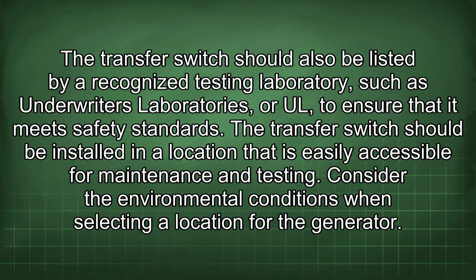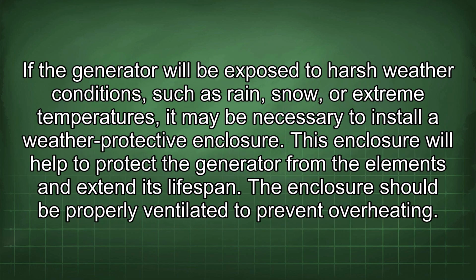Consider the environmental conditions when selecting a location for the generator. If the generator will be exposed to harsh weather conditions such as rain, snow, or extreme temperatures, it may be necessary to install a weather protective enclosure. This enclosure will help to protect the generator from the elements and extend its lifespan. The enclosure should be properly ventilated to prevent overheating.